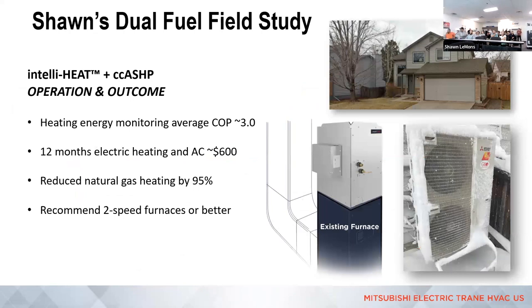As we go forward, here's my dual fuel system. I do have a furnace, but I don't use it because the heat pump outside takes care of it. I've knocked off 95% of my gas heating because I've got a beta version of this coil, and that beta version forces me to change over at 9 degrees. But I still have 50% capacity left on my heat pump at 9 degrees, sort of like that other chart I showed you. So I'm literally going to take out the furnace and put in a regular air handler, just like that full-size air handler there, and I'm not going to have backup heat because I proved to myself the system will do it.